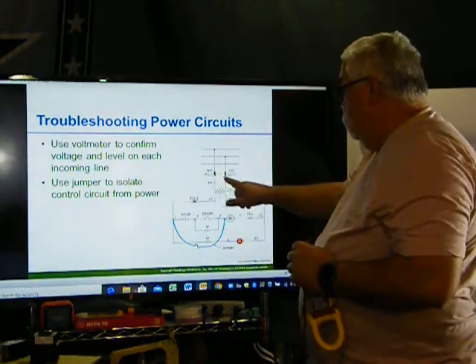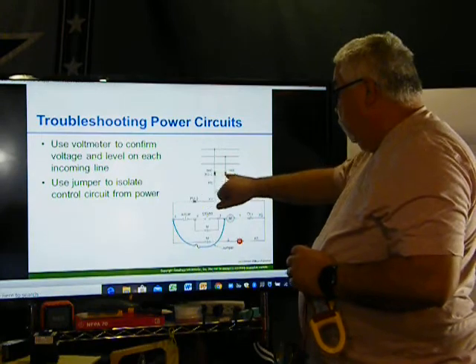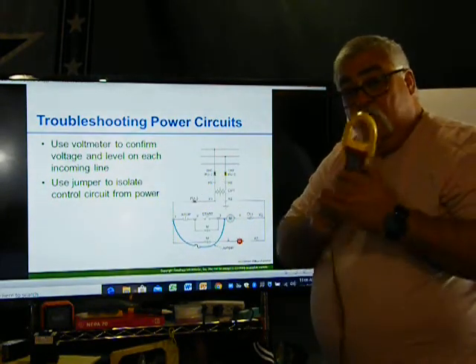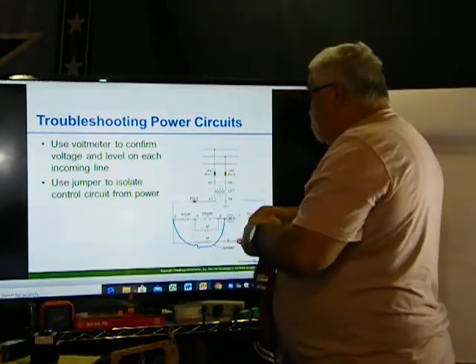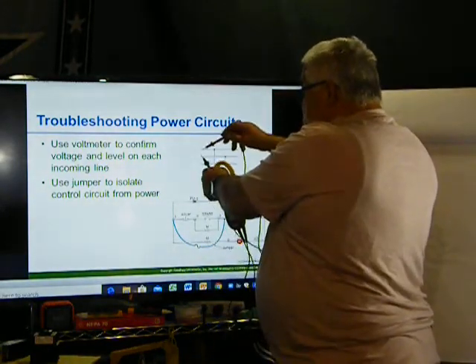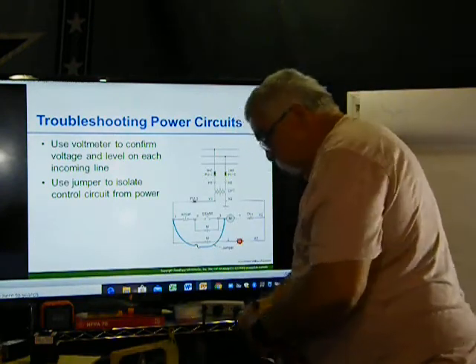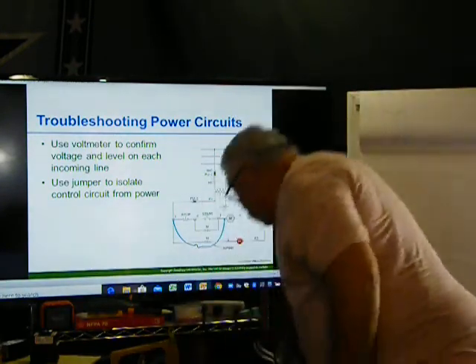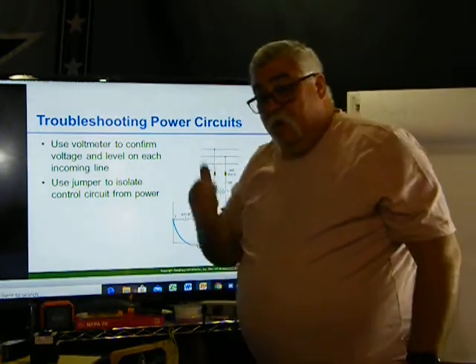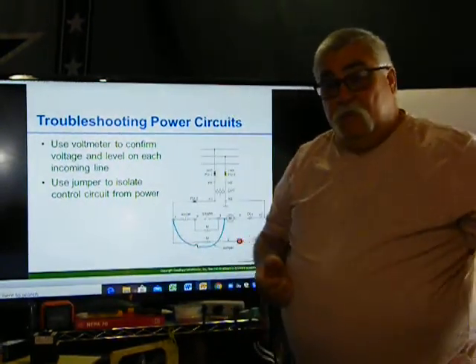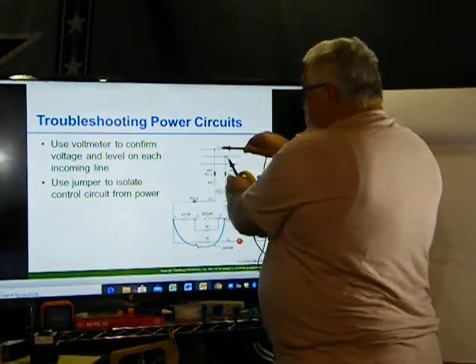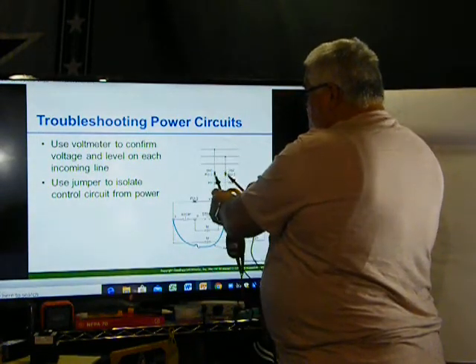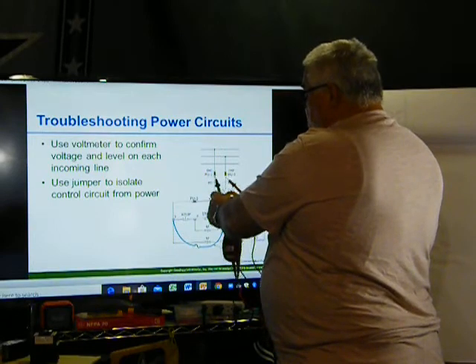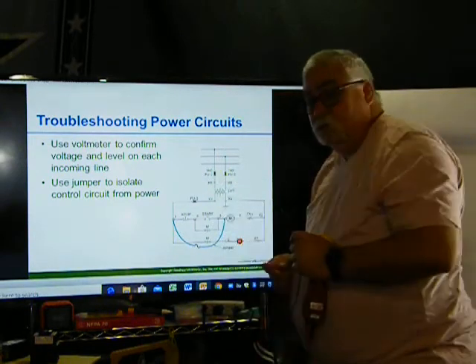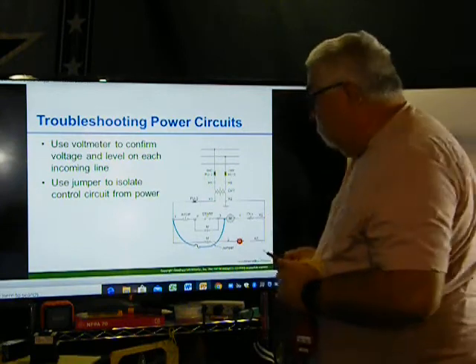You have to measure across, in order to read from this phase to this phase, and you should get your applied voltage. So if you go to the main breaker, which is up here, and I go to this breaker and touch across here, I've got 480 volts. So now I know what my applied voltage is, 480 volts. So I should be able to measure it here to here, here to here, here to here. If I'm not getting it down here, obviously one of my fuses is not working.